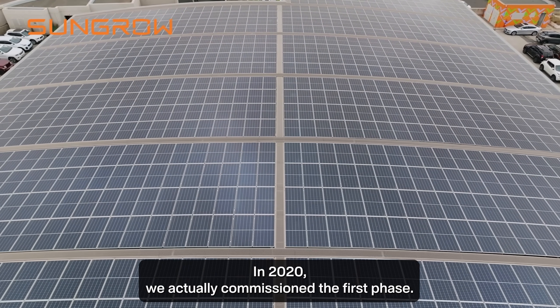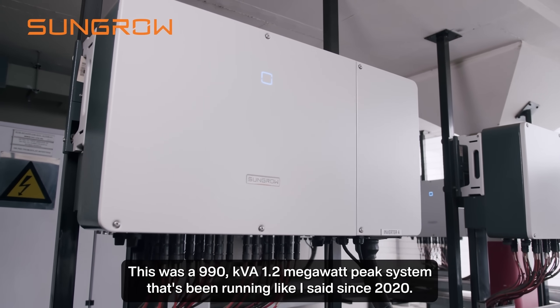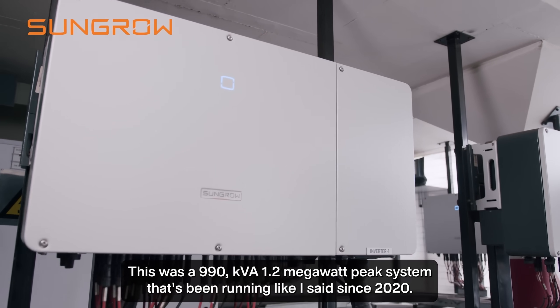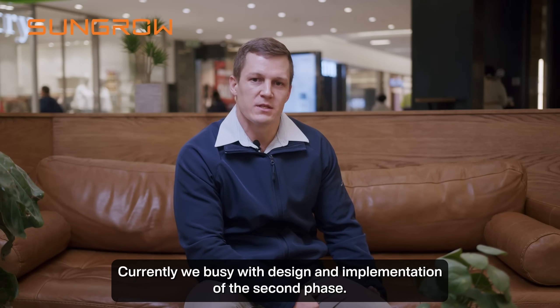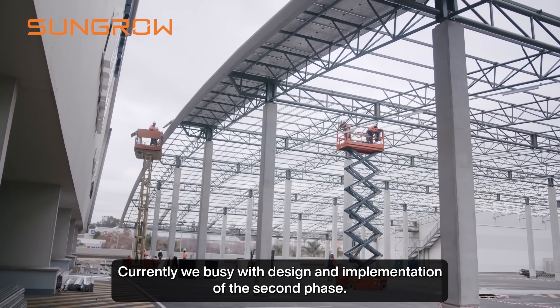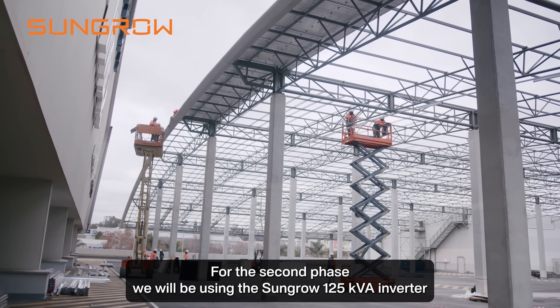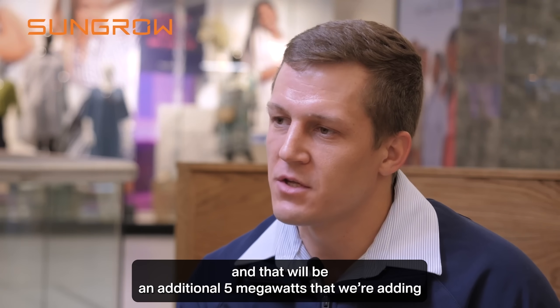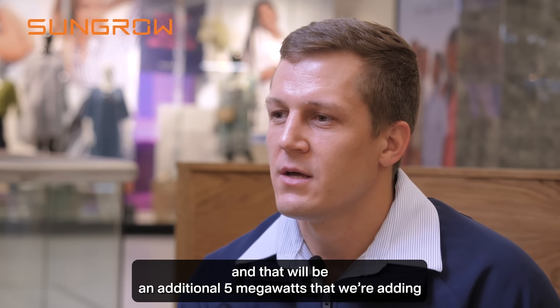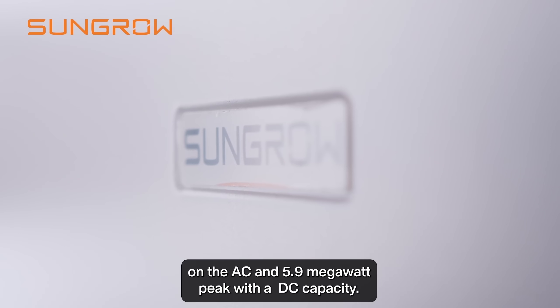In 2020 we commissioned the first phase — a 990 kVA, 1.2 megawatt peak system that's been running since 2020. Currently we're busy with the design and implementation of the second phase. For the second phase we'll be using the SunGrow 125 kVA inverter, which will add an additional 5 megawatts on the AC side and 5.9 megawatt peak worth of DC capacity.